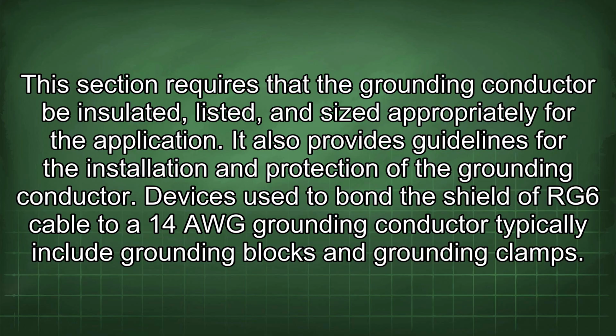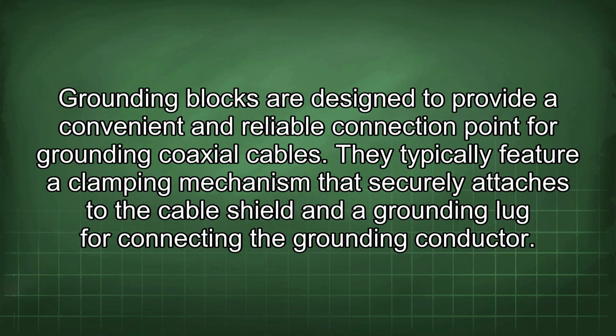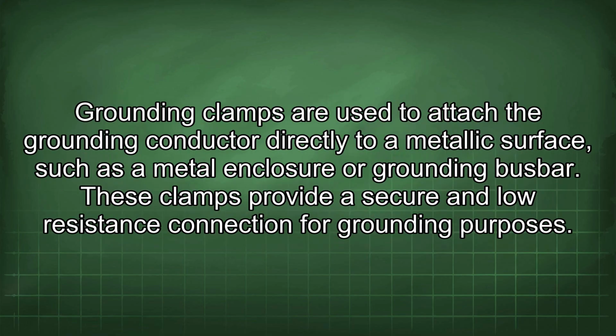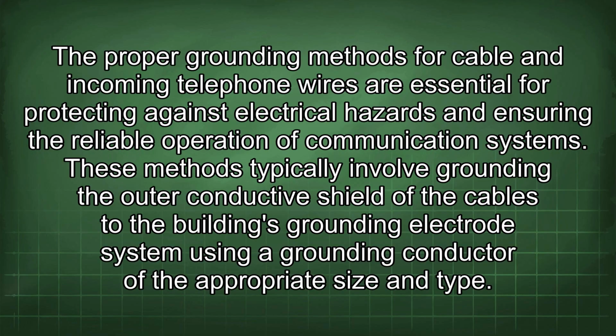Devices used to bond the shield of an RG6 cable to a 14 AWG grounding conductor typically include grounding blocks and grounding clamps. Grounding blocks are designed to provide a convenient and reliable connection point for grounding coaxial cables. They typically feature a clamping mechanism that securely attaches to the cable shield and a grounding lug for connecting the grounding conductor. Grounding clamps are used to attach the grounding conductor directly to a metallic surface, such as a metal enclosure or grounding bus bar. These clamps provide a secure and low-resistance connection for grounding purposes. The proper grounding methods for cable and incoming telephone wires are essential for protecting against electrical hazards and ensuring the reliable operation of communication systems.